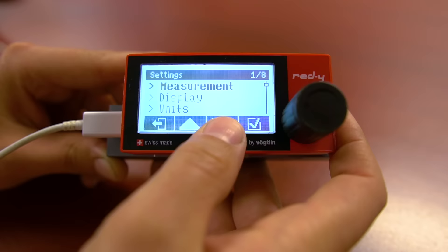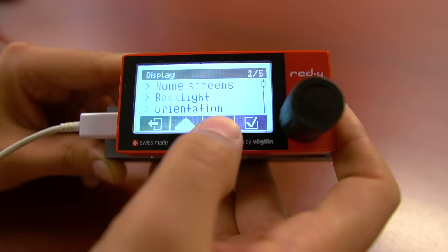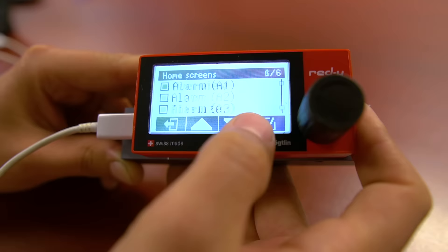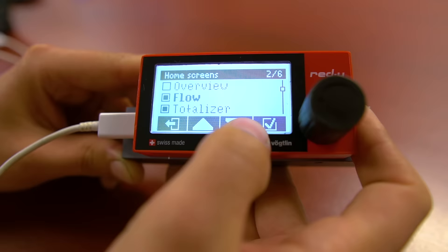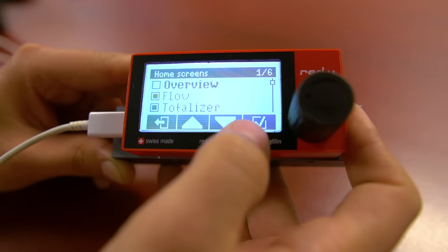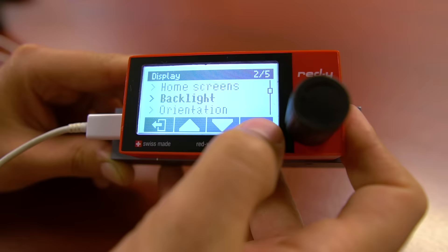The display menu is where you can choose which home screens you want, backlight settings, orientation of the screen, and how long you want the display to stay on for. All home screens are selectable — you can choose them by pressing the checkmark. When the unit is being powered by 24 volts or micro USB, the backlight brightness can be adjusted. Orientation allows the user to rotate the display so that it can be read in any installation, or leave it on auto so when you turn the unit the screen will automatically rotate.